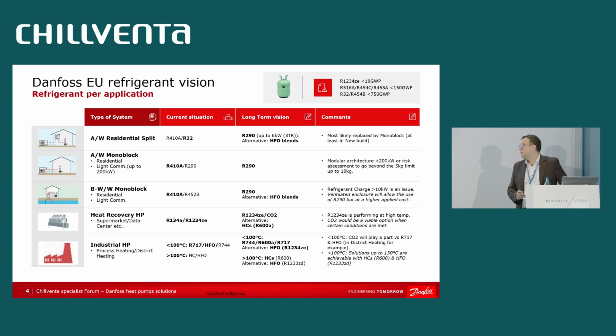For water-to-water, especially in the residential market, a certain part will be propane. We've developed solutions in our portfolio able to reach 5 to 6 kilowatt heating capacities with 150 grams of refrigerant. Above this, risk assessment needs to be done by the OEM, or in case HFOs are still around, blends could be used, such as R454C.